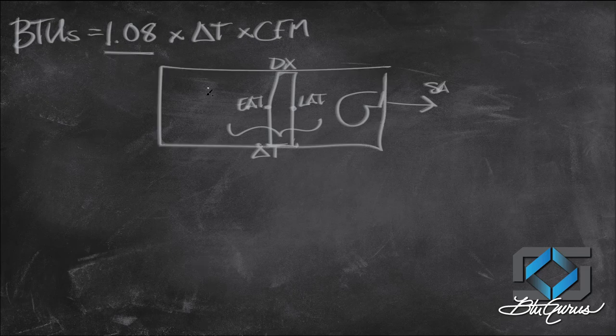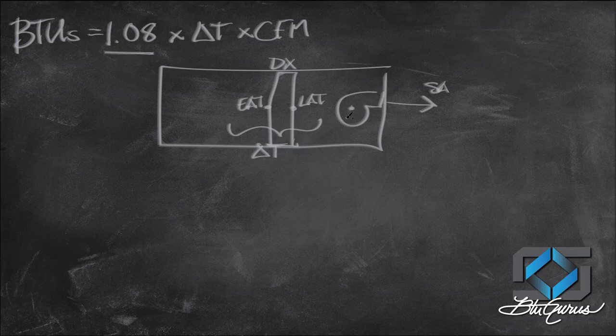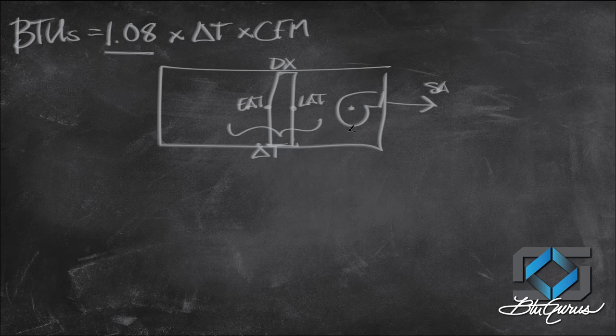There could be filters, there could be a lot of other stuff. I know someone's probably going to point out there's motor heat that usually will raise your supply air versus your LAT, but that's okay. Right now I'm just going to size up what this coil is going to do by using this equation.